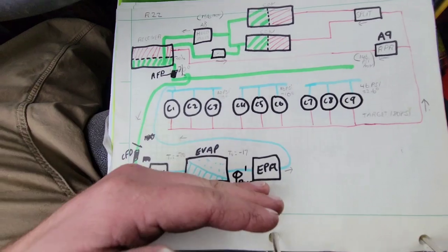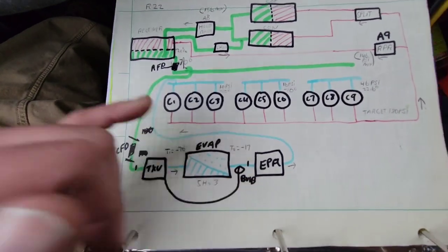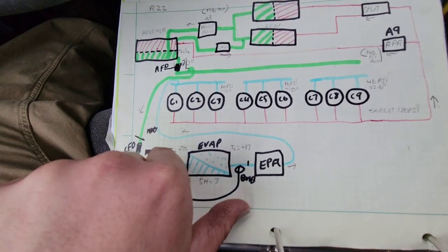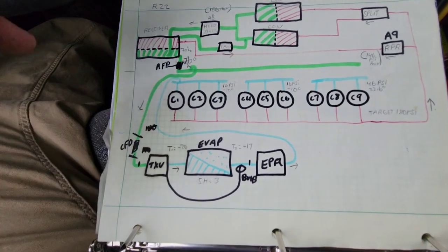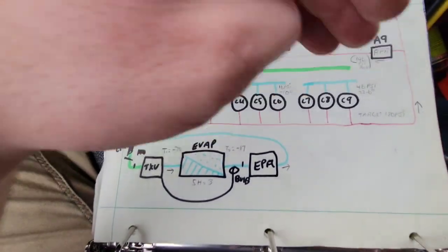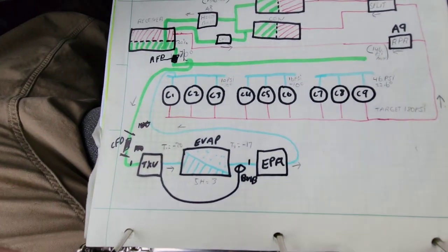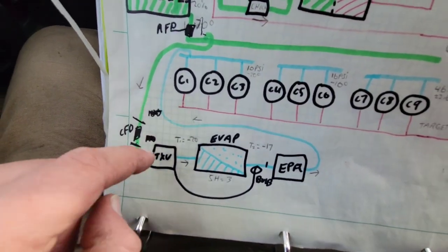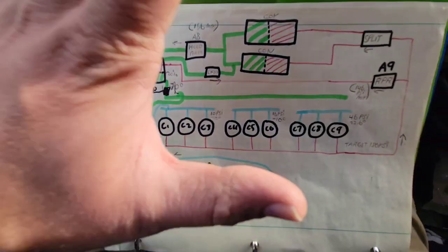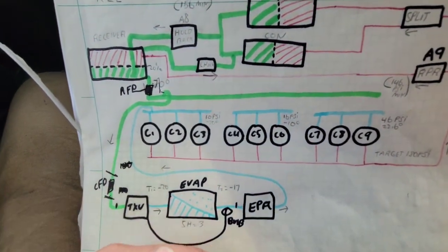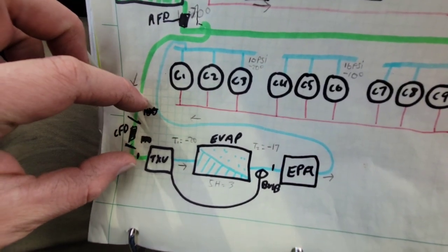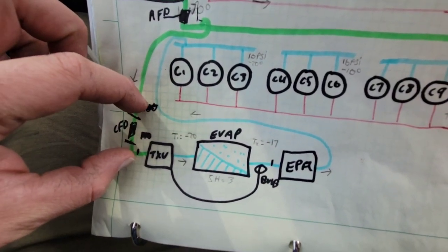So we actually had to lower the entire suction group of the rack. So it's very important that you check the pressures here, make sure they're proper. Then you check the hand valve, and then you check the filter dryer. And now I'm going to go into what I was going to say about the filter dryer before. Check this filter dryer, because this is the next thing in the lineup that would impede flow of refrigerant to your system. So we check the temperature differential across this case filter dryer.